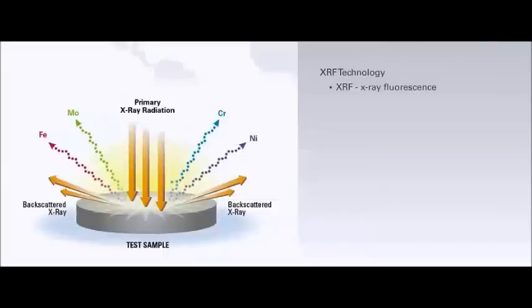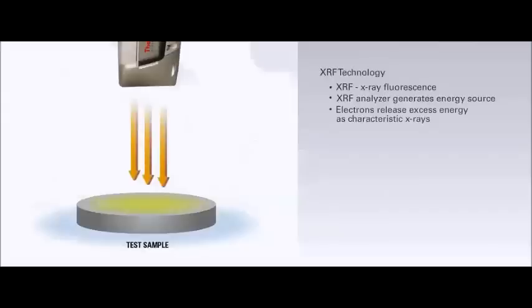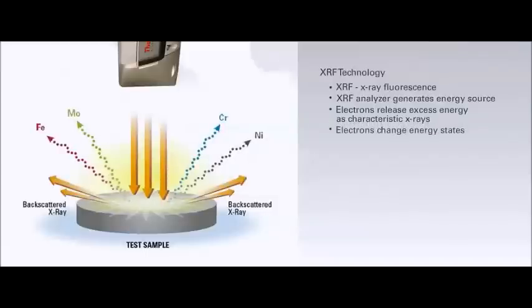The analyzers operate using energy dispersive x-ray fluorescence (EDXRF) analysis. Samples are excited by high-energy photons produced by the XL3 source. Sample chemistries are quickly and non-destructively determined as the characteristic fluorescent x-rays for each element, plus Compton and Rayleigh scatter from the sample, are measured simultaneously by the x-ray detection system.